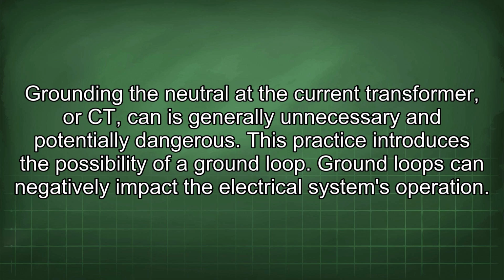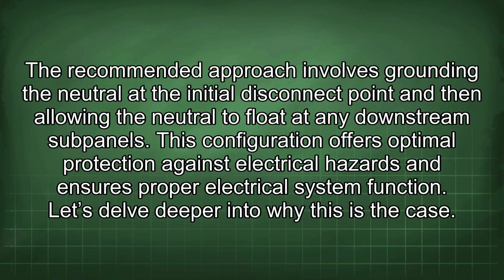This practice introduces the possibility of a ground loop. Ground loops can negatively impact the electrical system's operation. The recommended approach involves grounding the neutral at the initial disconnect point and then allowing the neutral to float at any downstream subpanels. This configuration offers optimal protection against electrical hazards and ensures proper electrical system function. Let's delve deeper into why this is the case.